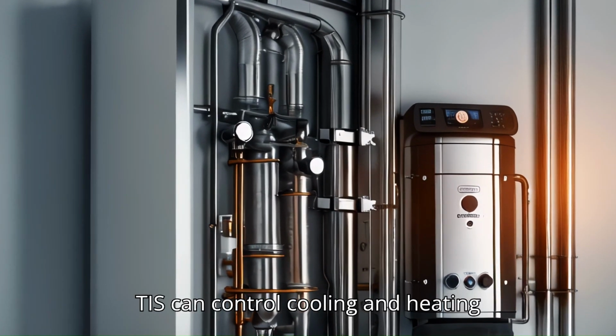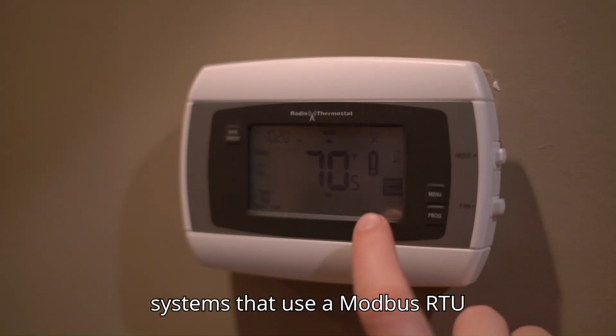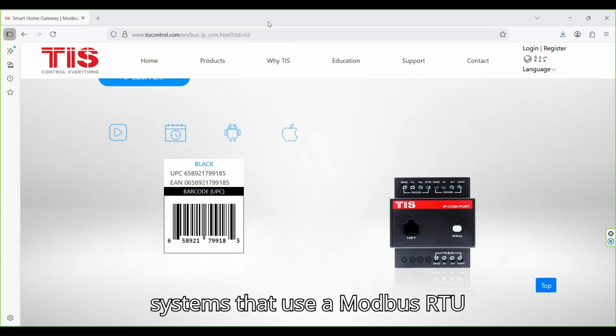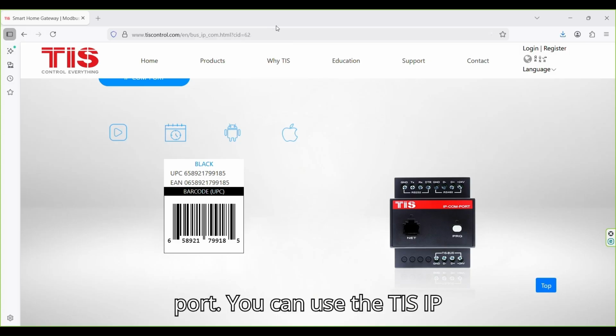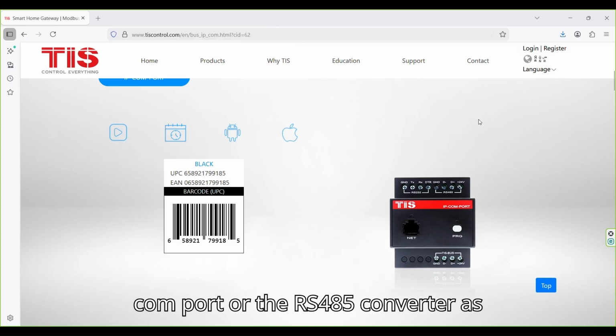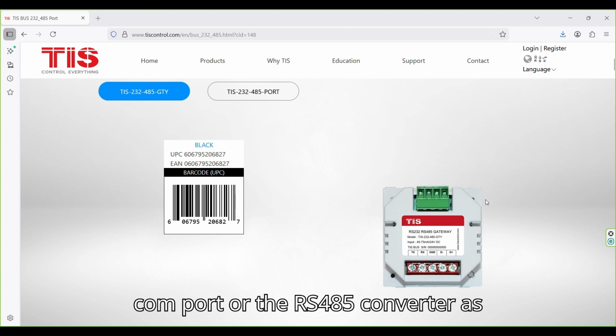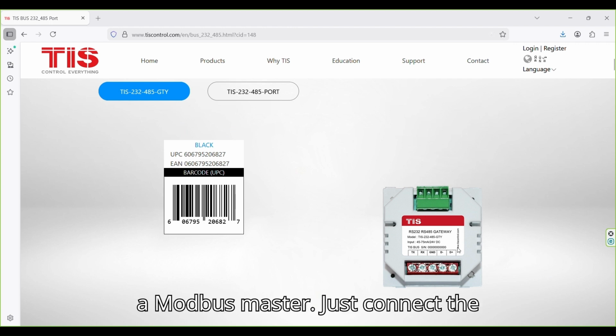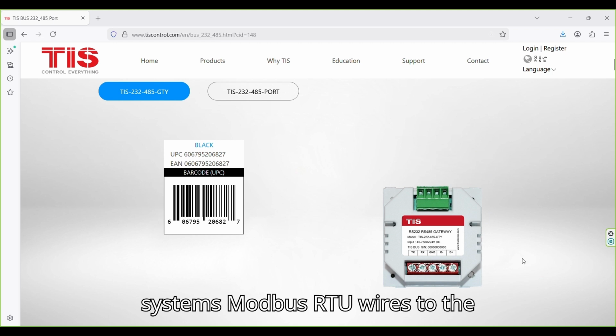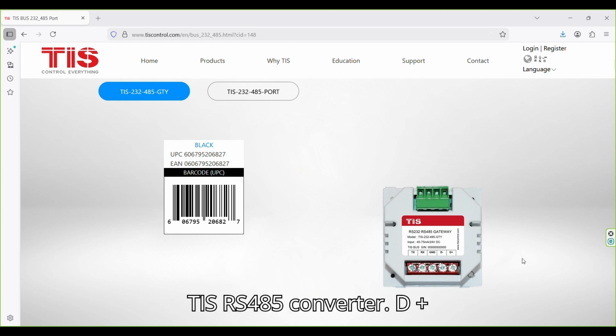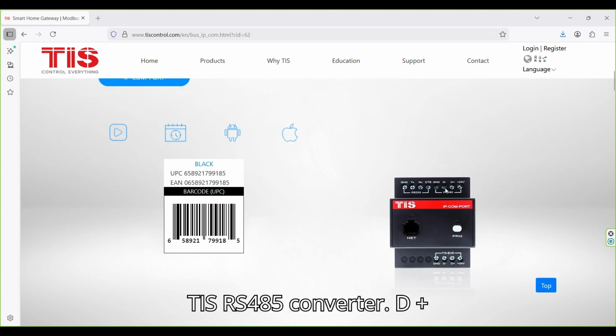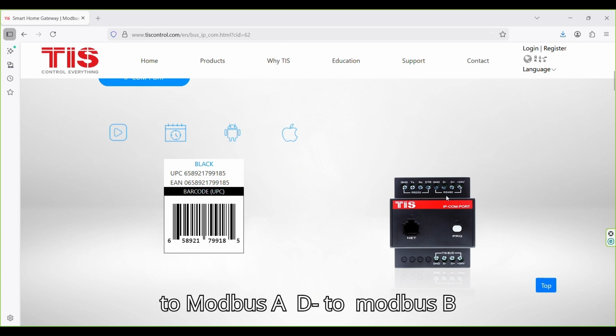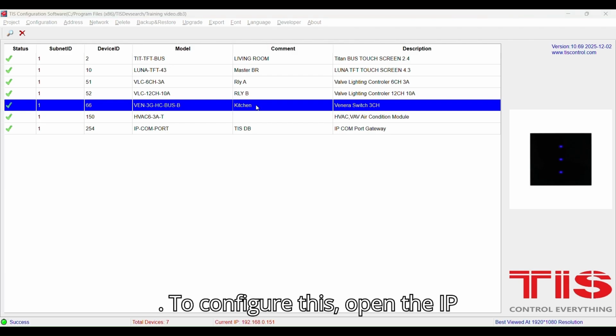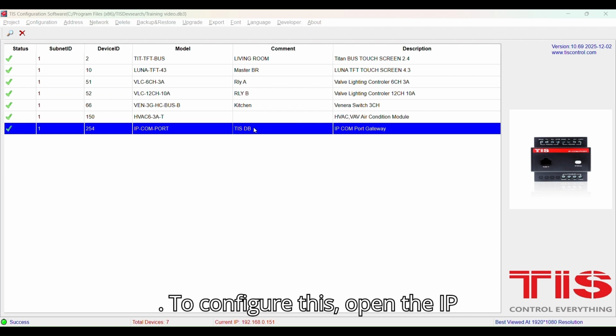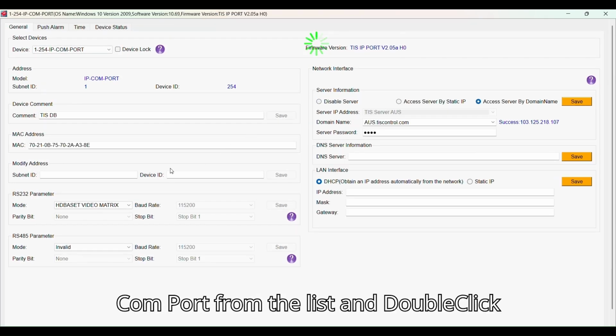TIS can control cooling and heating systems that use a Modbus RTU port. You can use the TIS IP COM port or the RS485 converter as a Modbus master. Just connect the system's Modbus RTU wires to the TIS RS485 converter, D+ to Modbus A and D- to Modbus B. To configure this, open the IP COM port from the list and double-click it.